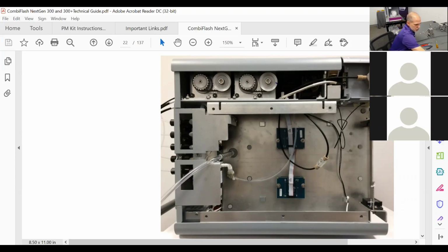Oh, and here you can see that shipping screw for the fraction arm that's inserted on this unit. This is a drain tube. So if you do leak in your fraction collector area, it leaks out of this clear tube, and it's usually routed right through there to the back of the unit.